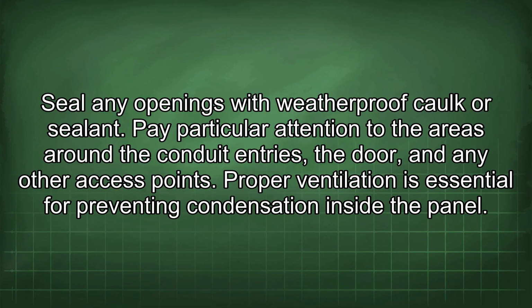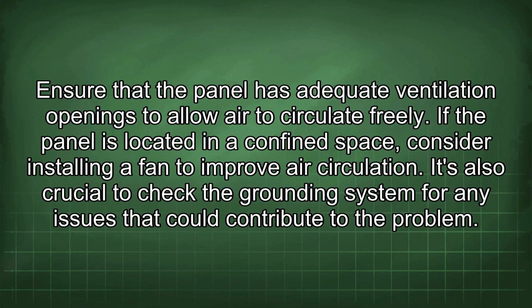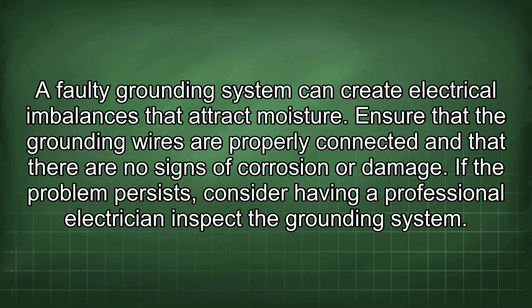Proper ventilation is essential for preventing condensation inside the panel. Ensure that the panel has adequate ventilation openings to allow air to circulate freely. If the panel is located in a confined space, consider installing a fan to improve air circulation. It's also crucial to check the grounding system for any issues that could contribute to the problem. A faulty grounding system can create electrical imbalances that attract moisture.